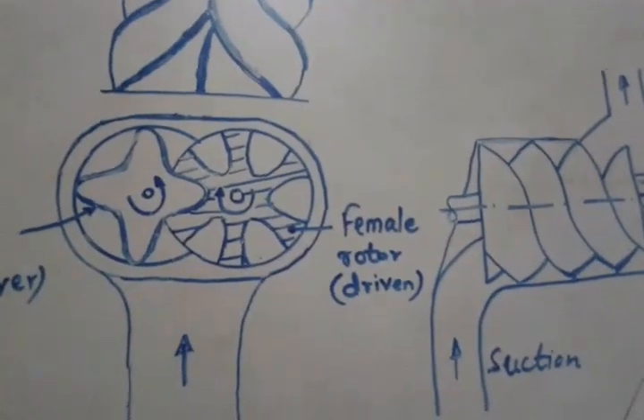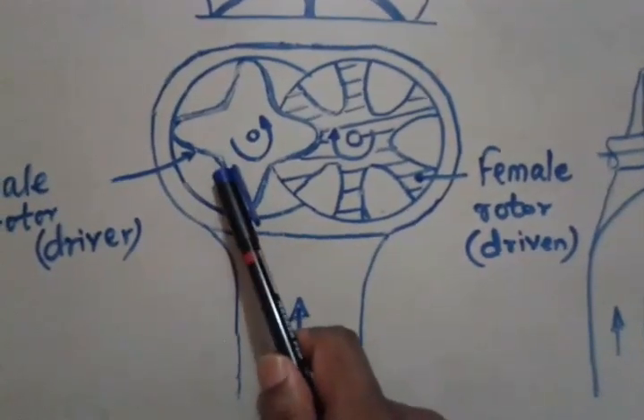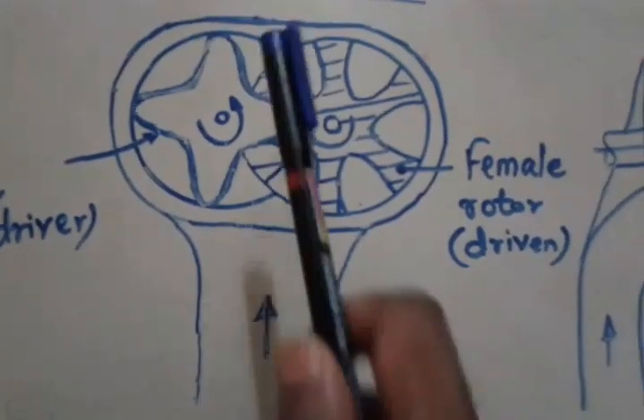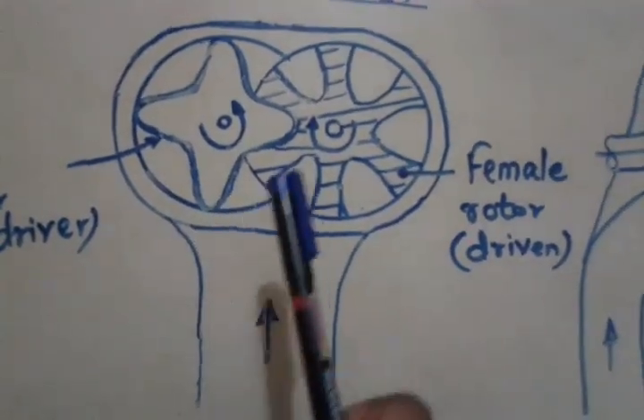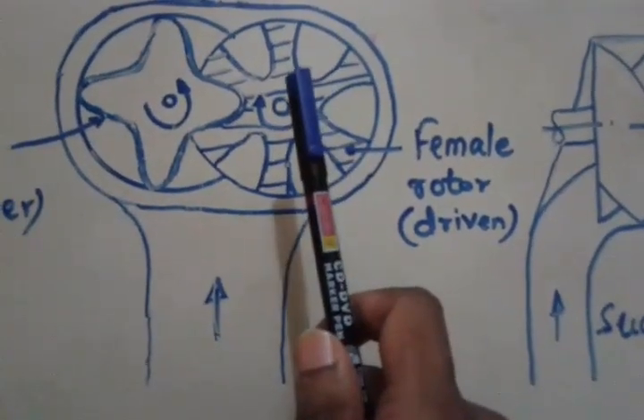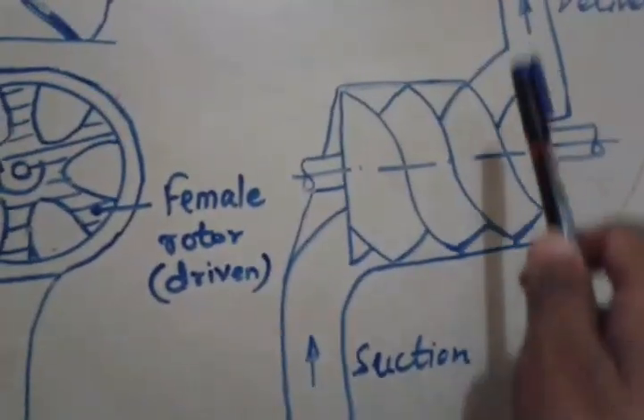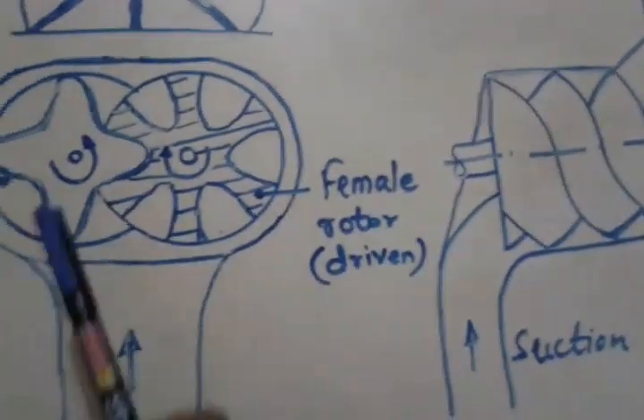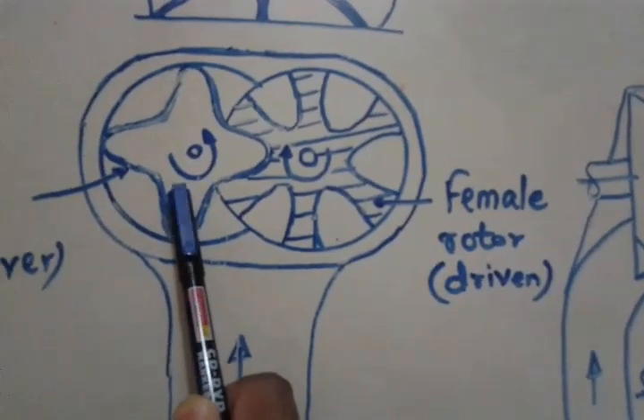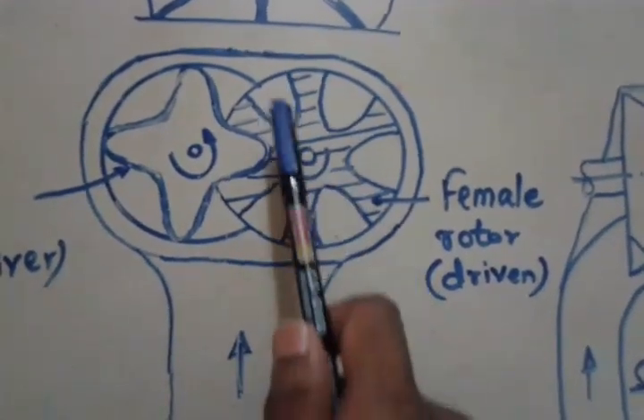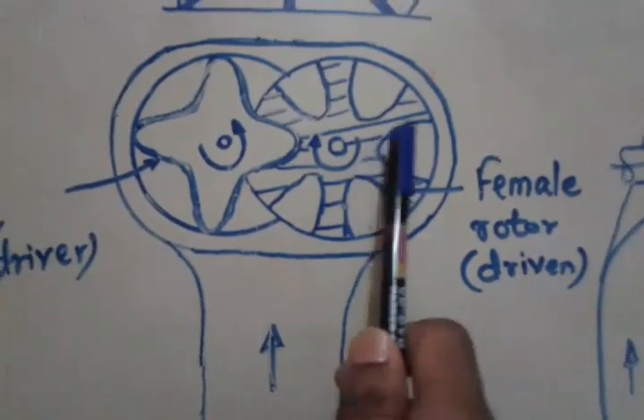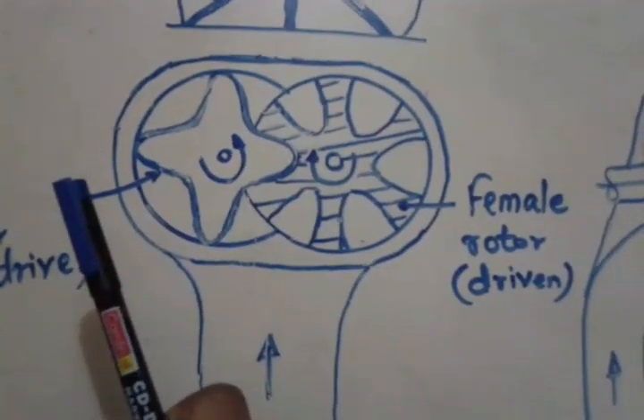Let us discuss the working. When the driving rotor rotates, the housing nearest to the suction end gets opened and the air is filled. The air which is so trapped is moved axially as well as radially with the rotation of the rotors and gets compressed. Air gets compressed until it reaches the delivery end. As the number of lobes of the male rotor and the number of gullies of the female rotor are different, the male rotor and the female rotor have different speeds.